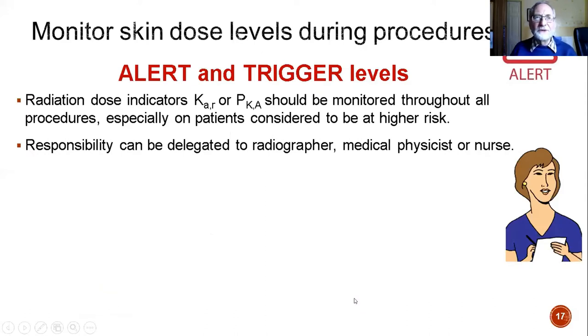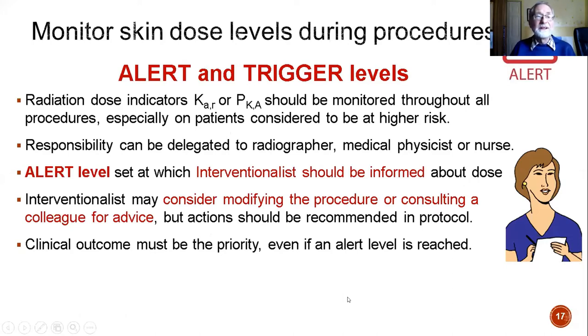So we want to monitor this dose level. We want to set something, and if we get to that level, then we have an alert. Using the cumulative air kerma, we can monitor that throughout the procedure, especially on patients considered to be at higher risk. This responsibility might be delegated to a radiographer, medical physicist, or nurse. An alert level is set at which the interventionist should be informed about the dose, then they may consider modifying the procedure, or they might consult a colleague, but whatever, the actions could be recommended in a protocol. The clinical outcome must be the priority, even if an alert level is reached.